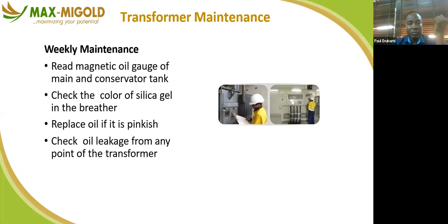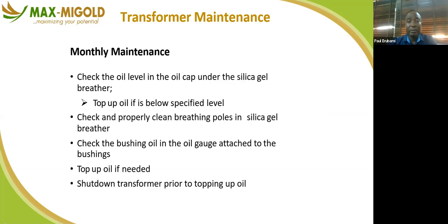So we have different types of maintenance on our transformer. These are the things you carry out when you are carrying out maintenance on the transformer. You read the magnetic oil gauge. If it goes below what is expected, you flag it up and they top it up. You check the color of the silica gel. The color is always something purple, but if it's changing color, you know that something is wrong, so you call for attention. If the oil is pinkish, you replace it. Check for oil leakage from any point of the transformer. These are the things your technician should pay attention to when carrying out maintenance work.